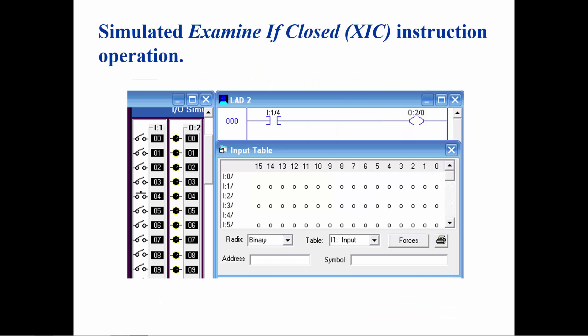When the switch is closed, a 1 is placed in the input table. The examine if closed instruction will allow rung continuity through itself, much like a closed relay contact allows current to flow. The address of the contact turns yellow, indicating logic continuity.